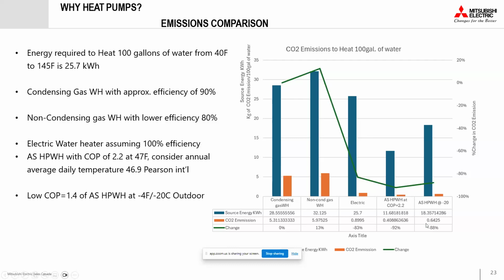or lower. Still, if you see the orange bars for the CO2 emission, we can still reduce. As compared to gas to electric, it's like an 83% reduction. In terms of energy consumption here, from electric to heat pump, it's like 650, more than 50% reduction in terms of the electric consumption. So both energy consumption and carbon emission are reduced with the use of those electric heat pumps, even with that lower efficiency.